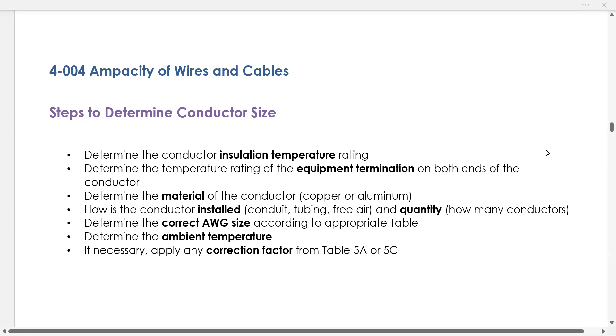Then you consider how it's installed. Is it in free air? You can probably carry more current in it because it's going to cool. Is it in conduit? Is it in tubing? And then there's some derating factors based on how it's installed. And how many conductors are in each of these when it's installed? And that matters to the heat that is generated.